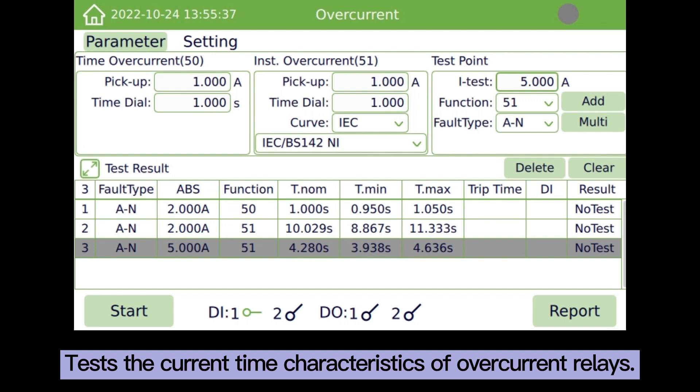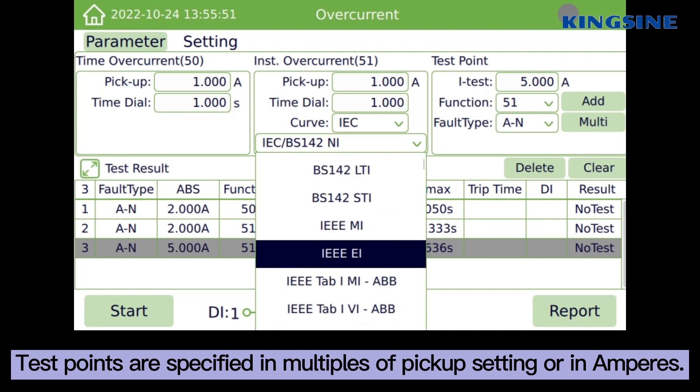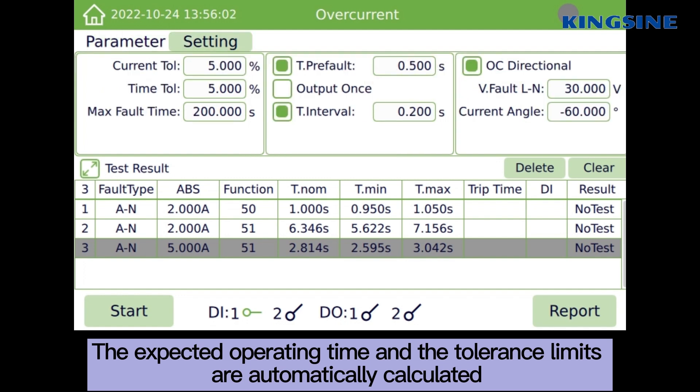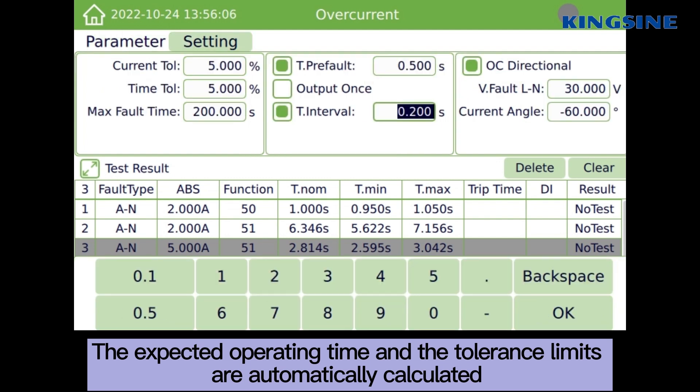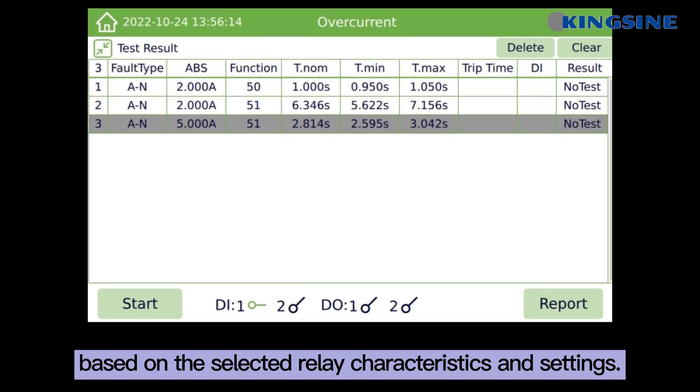Test the current time characteristics of overcurrent relays. Test points are specified in multiples of pickup setting or in ampers. The expected operating time and the tolerance limits are automatically calculated based on the selected relay characteristics and settings.